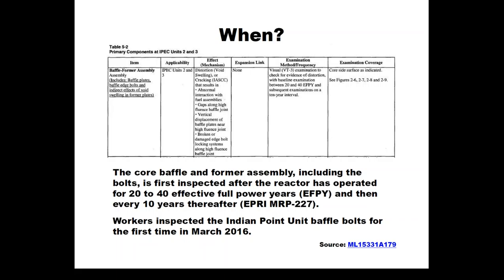Prior to these VT3 inspections conducted under this EPRI guidance document, owners were required to visually inspect the baffle bolts once every 10 years. The inspections being conducted at Indian Point and elsewhere now use ultrasonics for a more detailed examination. The prior visual inspections had only identified bad bolts on one occasion, meaning they were not very effective at identifying degradation that had been there for quite some time. The state of New York, through its involvement in the Indian Point re-licensing, is the primary reason why this improved inspection requirement is in place today. It has not yet been done on Indian Point Unit 3, which is scheduled for 2019.